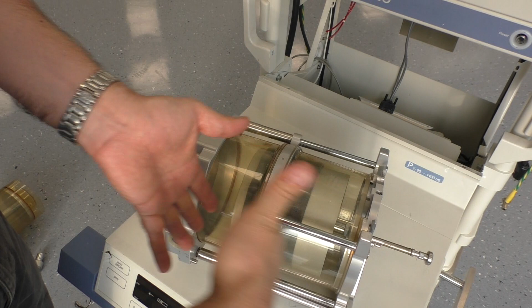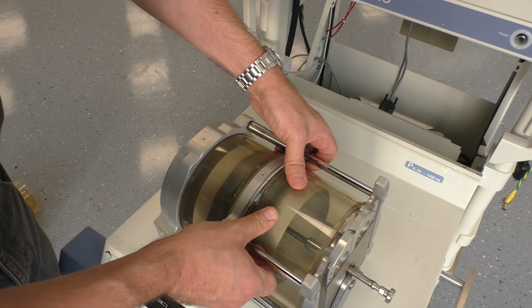So this here is a little bit unexpected. I expected to have a bellows that folds up and down, but this is more like a piston pump, but it has a rolling rubber gasket here, which rolls around the inner piston and seals it completely. So that's the way the gas mixture is pumped. What you adjust is how much it pumps, only a short way or the full way, depending on the size of the patient or of the patient's lung, or whatever you need to know. That's what you adjust here with the control box. Okay. Yes, it's very tight. Would be a good air pump anyway.